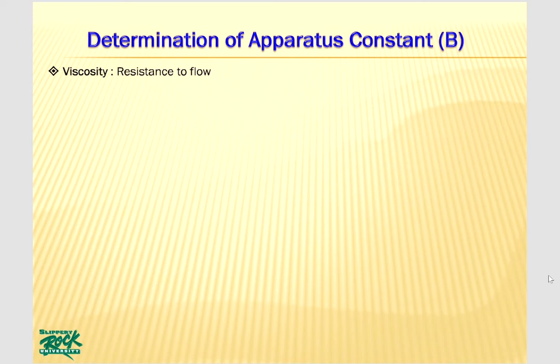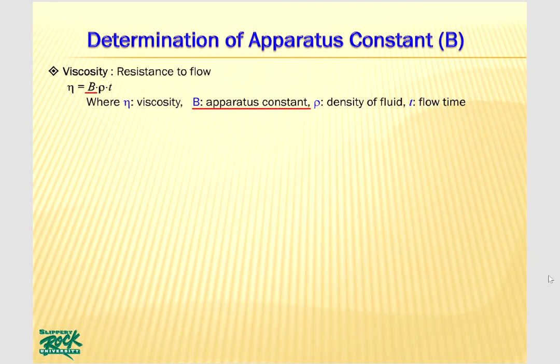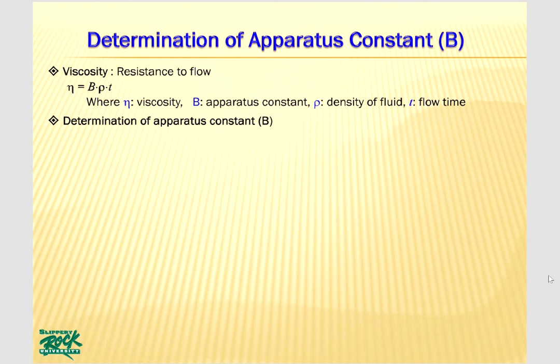Viscosity is defined as the resistance to flow, and it is directly proportional to the density of the fluid and to the flow time. So an equation of viscosity can be written as: viscosity Eta equals proportionality constant B times density of fluid rho times flow time T. The proportionality constant B is called the apparatus constant and it may be different from viscosimeter to viscosimeter. So you have to determine the apparatus constant first before you use a viscosimeter. I will show you how to determine the apparatus constant B.